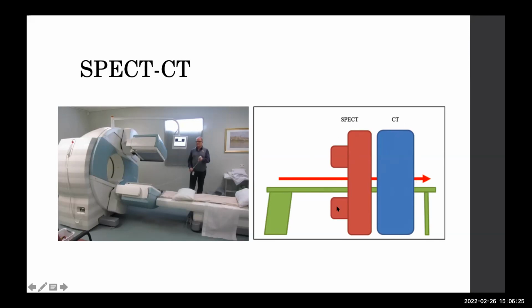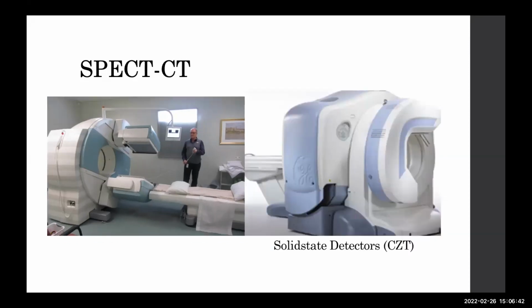And you can acquire the SPECT data and CT data. SPECT data is acquired in the conventional manner, because these are conventional sodium iodide crystals, very large detectors, and then you take tomographic images and then CT, and they get fused together. This is called SPECT-CT, which many hospitals are now acquiring, and it gives you both information of function as well as morphology. Here comes another type of camera. This is the conventional image. And this is the solid state detector SPECT camera, which you can see.